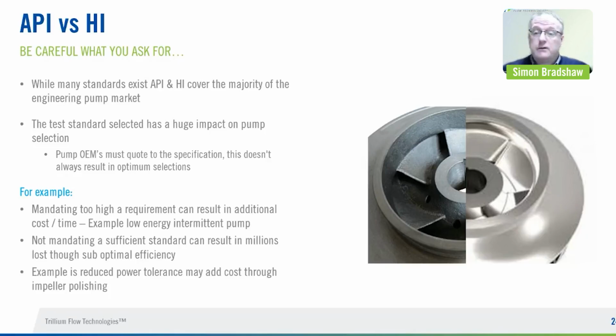That said, you don't want to specify a requirement that is more than you need, because it is going to cost additional lead time and additional cost in your purchasing. So, for example, a low energy intermittent pump, as was mentioned there, efficiency is not such a big deal for that over the lifespan of the pump, and you probably wouldn't be as worried about that.